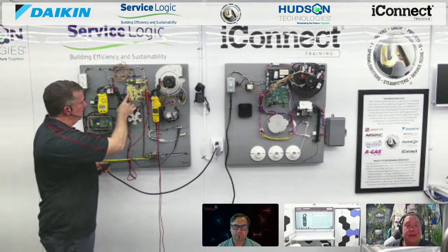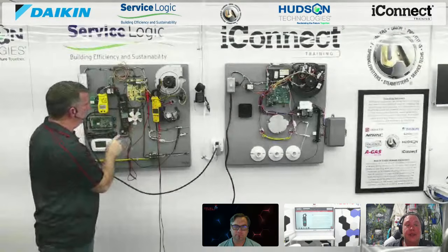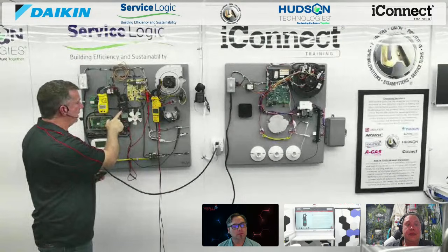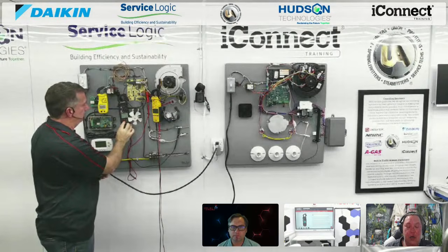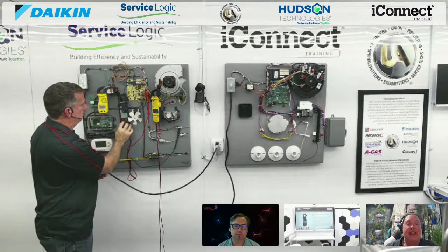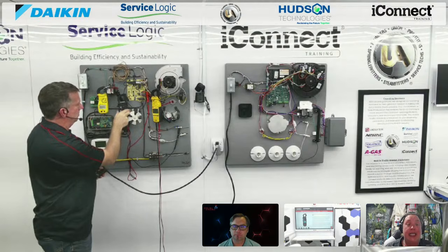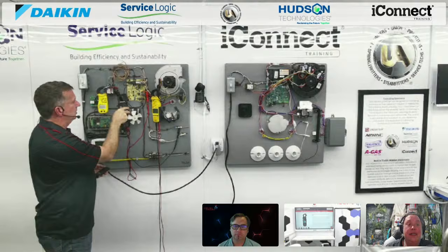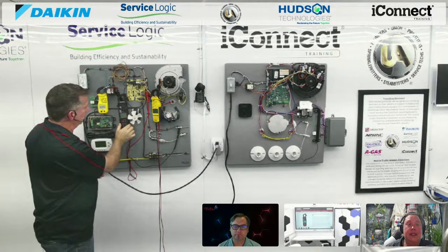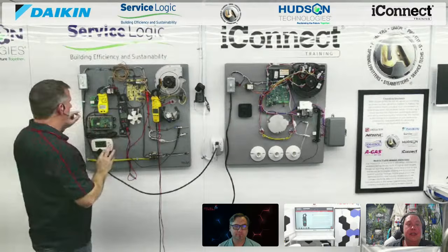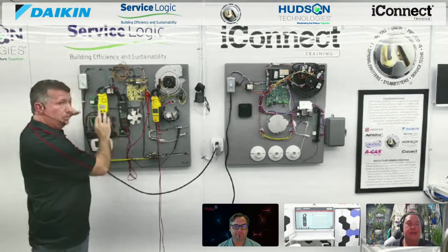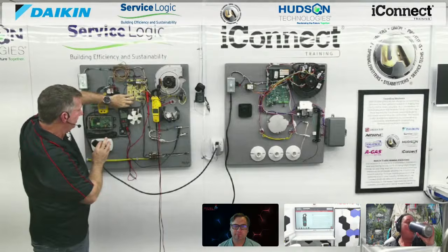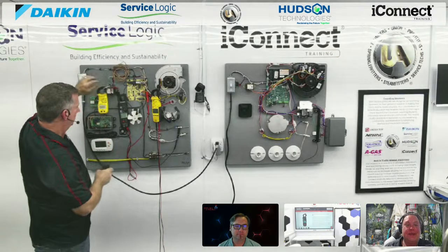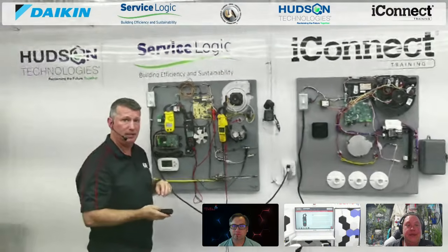Now I need to go out of my power factor mode, correct? Correct, and on that particular meter you go all the way down to the very bottom. You'll see volts, then off, then the low Z functionality. So let's make sure everyone sees what happens if I were measuring straight volts AC, let me zoom in a little bit.